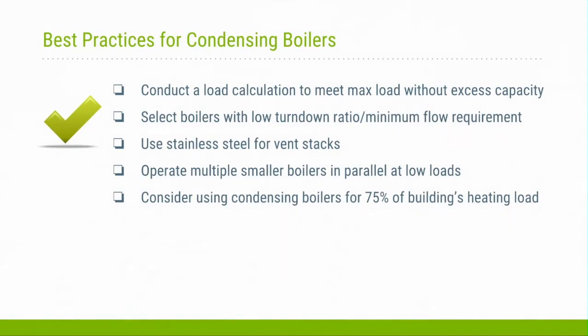So this is the best practices takeaway for condensing boilers if you're looking at installing them. Really look at conducting a load calculation to make sure you meet the maximum load without putting a whole bunch of excess capacity in. So actually do that engineering step. Select boilers with low turn-down ratio and minimum flow requirements. And so this goes to the fact that they operate better at these low turn-down ratios.